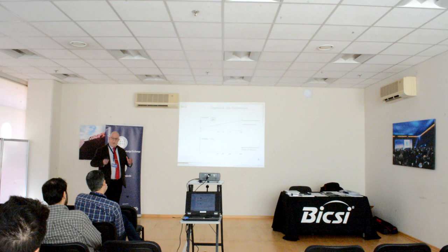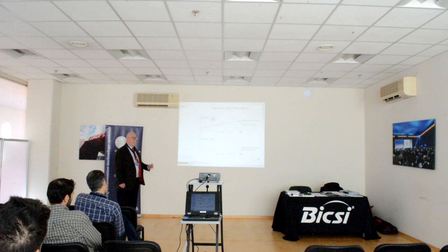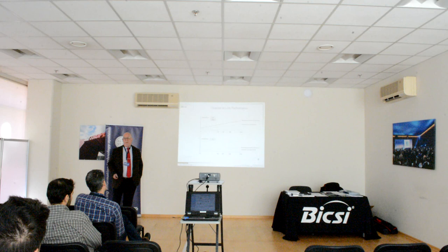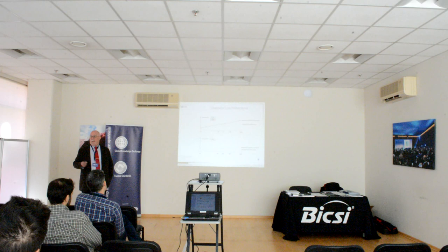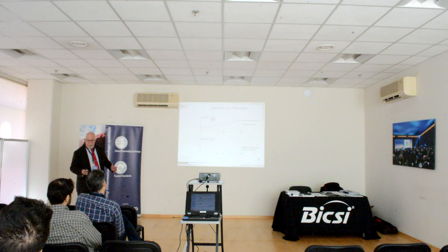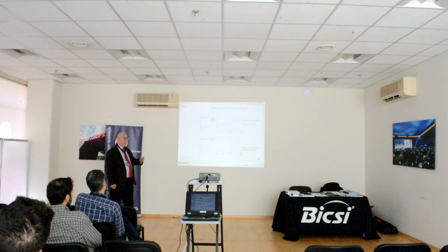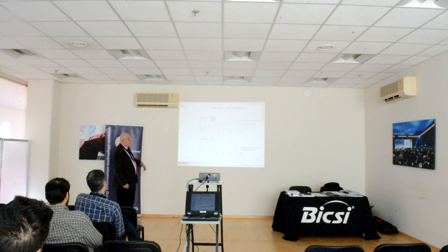And not very much more. And in truth, the specified attenuation is much higher than the expected attenuation because the cable's generally better and the connectors are better than the specification, which is why the specification is a maximum. So the general principle is that most attenuation values you're going to try and measure are lower than the maximum specified ones. And that's true for single mode as much as it is for multimode.